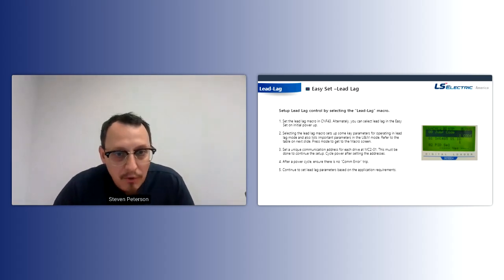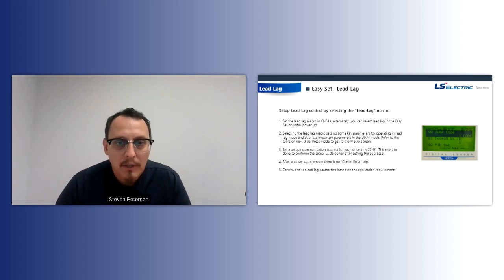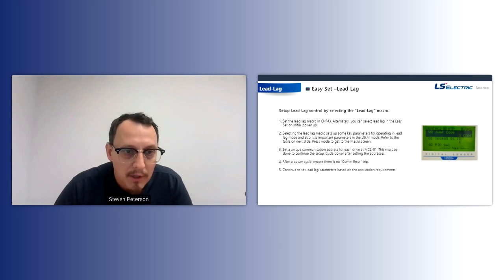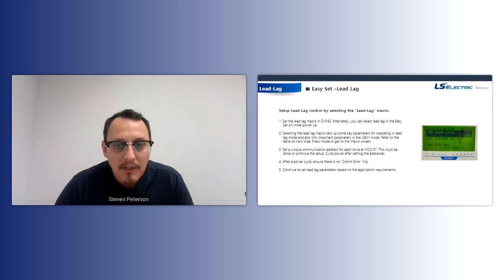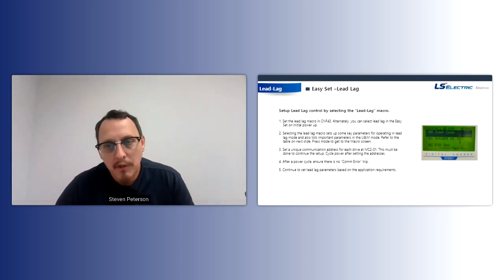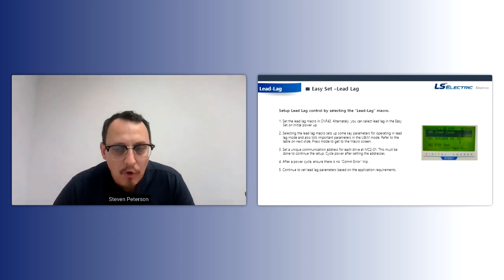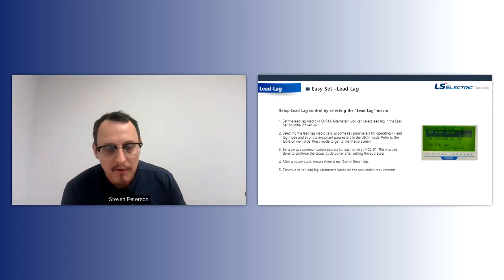The next thing you're going to need to do is enter some of the key parameters here. If you're going to operate in lead lag mode, you're going to go into this macro mode, which we call macro 2. And then I'm going to show you on the next slide what parameters are within that macro. Okay. And the first thing you need to do before you set up anything is your ID. So we're utilizing Modbus from drive to drive to drive. So if you have 2 drives, you're going to have drive 1, which is going to be address 1.